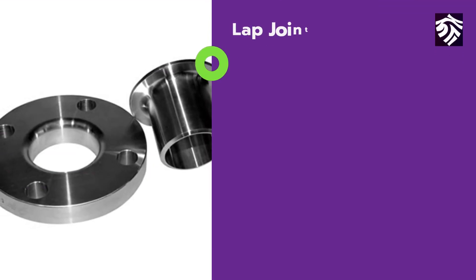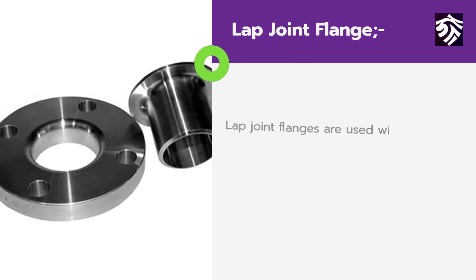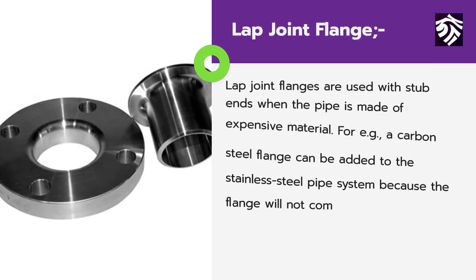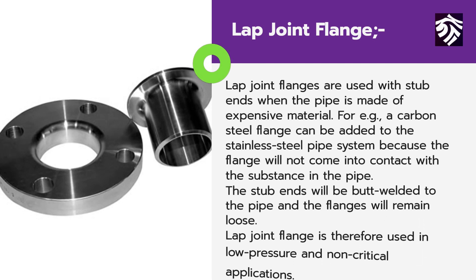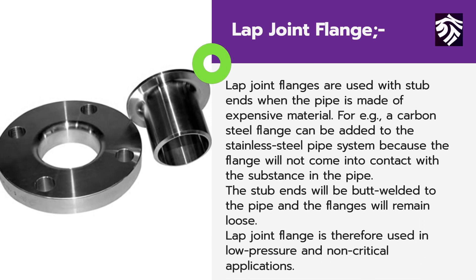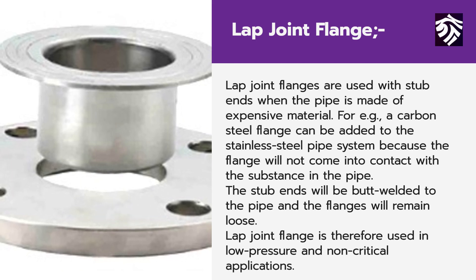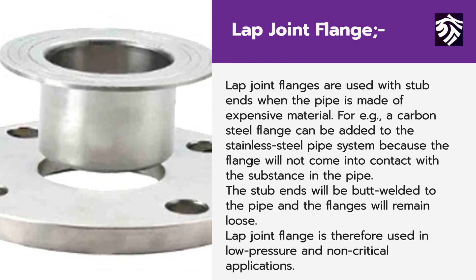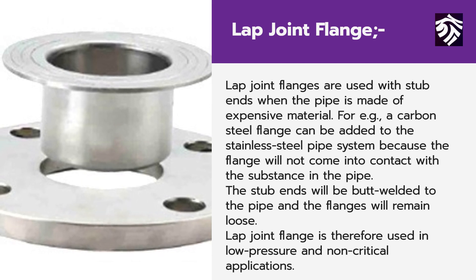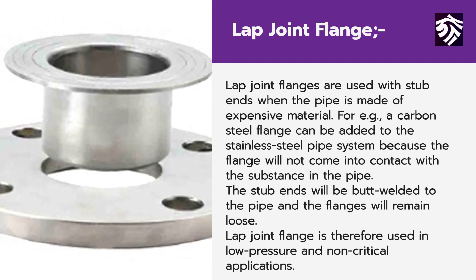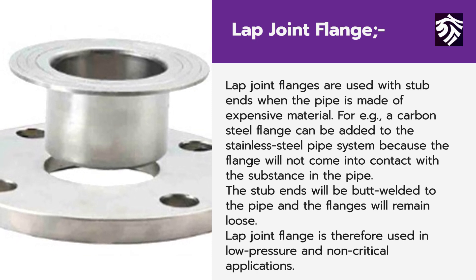Another special type of flange is the lap joint flange. Lap joint flanges are used with stub ends when the pipe is made of expensive material. For example, a carbon steel flange can be added to a stainless steel pipe system because the flange will not come into contact with the substance in the pipe. The stub ends will be butt welded to the pipe and the flanges will remain loose. Lap joint flanges are therefore used in low pressure and non-critical applications.